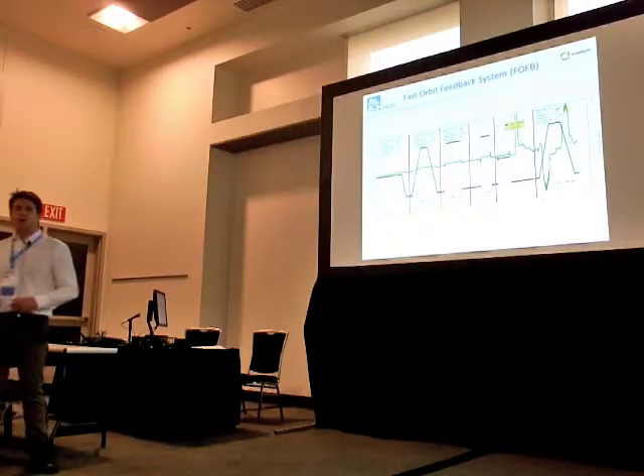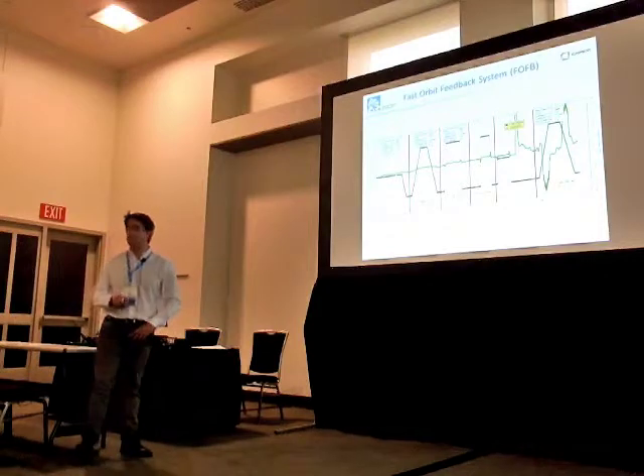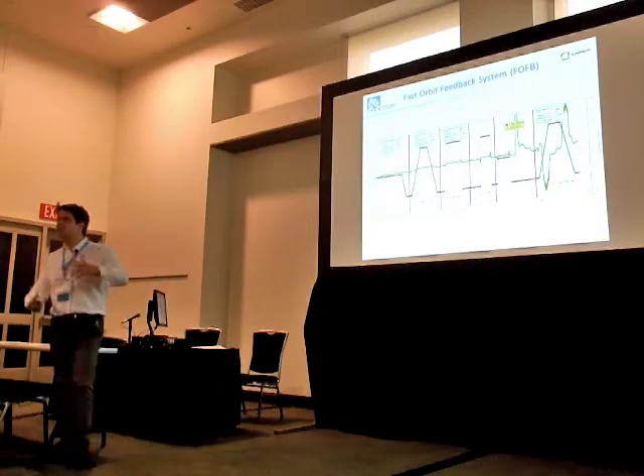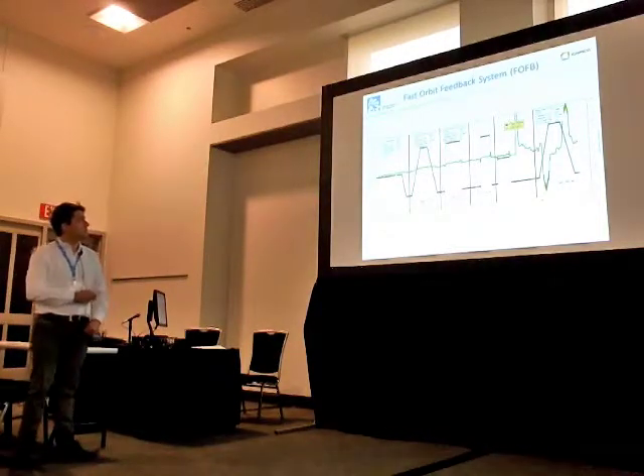This is to give an idea of when we have an insertion device: it basically changes magnetic fields on the electron orbit, and so causes a large number of perturbations. If we don't have a reliable correction system, you're all the time shaking the electron beam. So one user does an experiment, and the other has a beam completely shaken. So you have to have a system that corrects all the time.